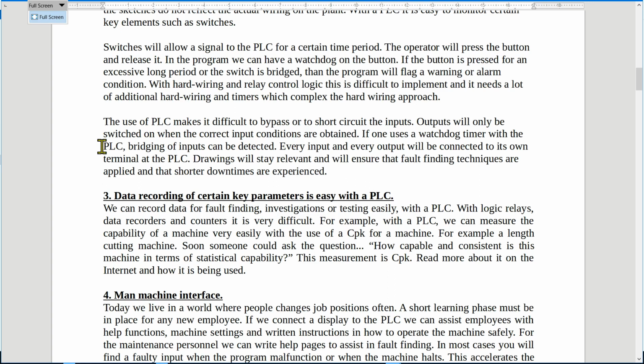Every input and every output will be connected to its own terminal at the PLC. Now the drawings, if you do this, the drawings will stay relevant and will ensure that fault-finding techniques are applied and that shorter downtime is experienced.